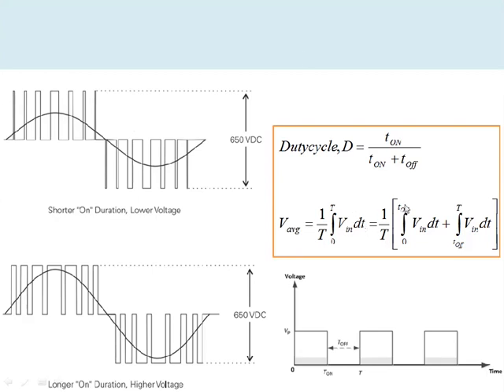A shorter on-duration generates lower voltage and a longer on-duration generates higher voltage. Within a fixed time period T — which depends on the frequency — if the on-time is more, the average voltage is high; if the on-time is less, the average voltage is low. In this way, PWM controls both voltage and frequency in the VFD.